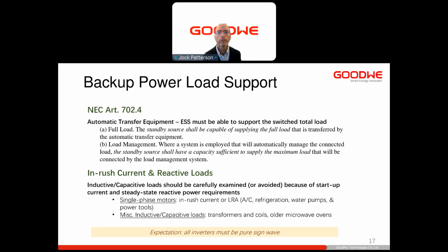In providing equipment to do the transfer and support the load from the grid to your backup system, this equipment must be able to handle and be rated for that kind of use and load. So in calculating your loads, be very mindful of ones that are reactive loads. These are loads that can use more power than you think, but they don't actually consume. They draw a lot of power, but they don't consume it all, so it can be misleading. You need to pay attention to those type of loads and highly variable resistive loads that have a high inrush current. Most will have a nameplate rating showing that, but we'll talk about how you can also just measure these devices for their power demands. Whatever your solution, absolutely use a pure sine wave inverter.